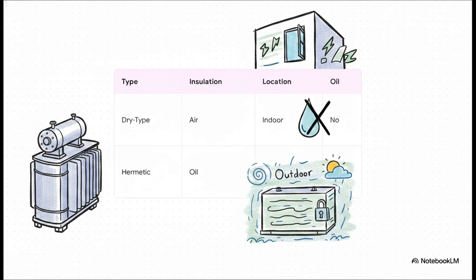All this protection leads us to our next major engineering choice, which is where we place the transformer and how we house it. We've got a strict divide here based on the environment. First up, we have dry-type transformers. These use air or cast resin insulation and skip oil entirely. And hey, no oil means no tanks to leak. Then we have hermetically sealed tanks. These are fully oil-filled and completely gas-tight. Oil is a fantastic medium for cooling and insulation, and since it's hermetically sealed, there is absolutely no room for the oil to breathe or absorb moisture from the outside air. That makes them the ultimate go-to choice for outdoor distribution transformers that need to sit out in harsh weather and give you decades of maintenance-free service.